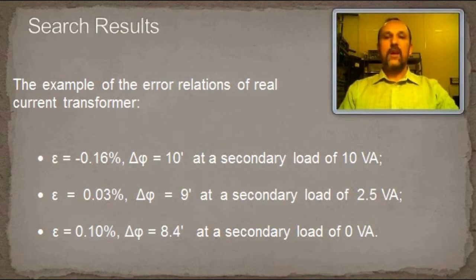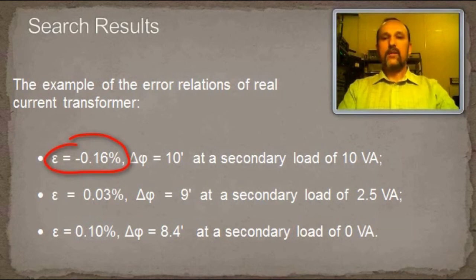The current transformers are designed in such a way that ratio error is negative at maximum load, and it is positive at 0 load. In such case, the phase displacement will most often have the same sign.